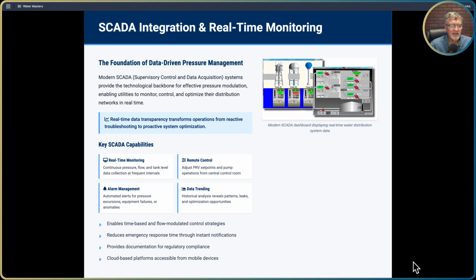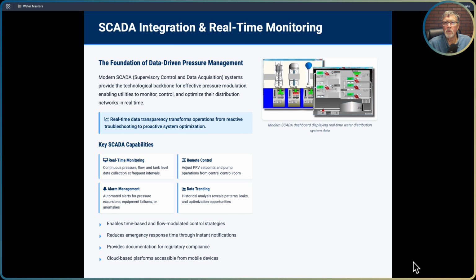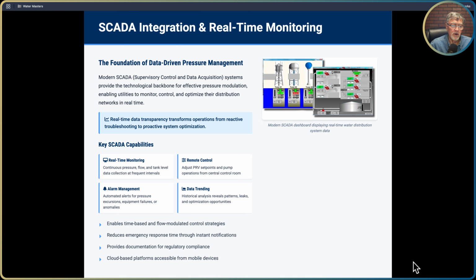What's not to like? Real-time data transparency transforms operations from reactive troubleshooting to proactive system optimization. So we're pounding that point in again: we want to go to proactive and then on to predictive analysis for our water systems. Data allows us to do that. Key SCADA capabilities we're looking at are real-time monitoring, alarm management, so being able to get the alarms out to the people even on their off hours, remote control, being able to adjust things by remote control, and data trends. And I would also say one of the things you want to have is the real time.